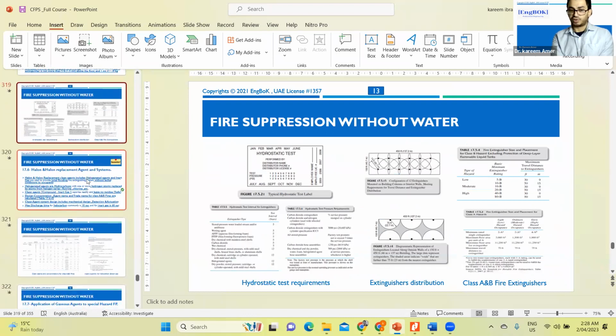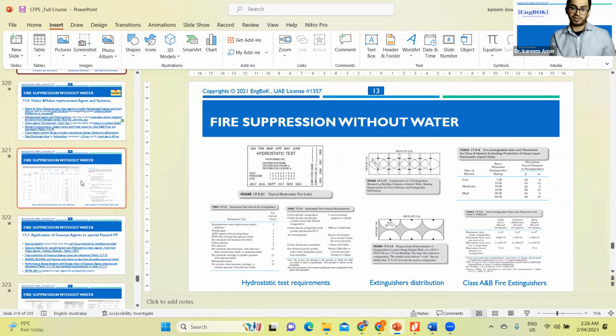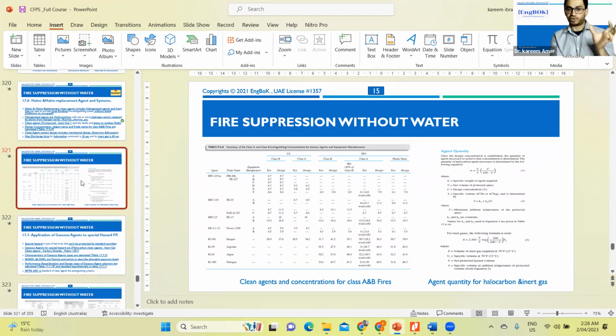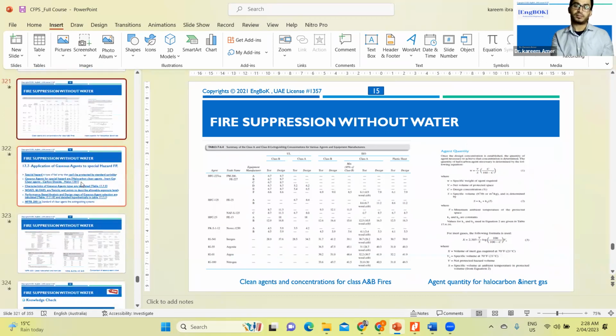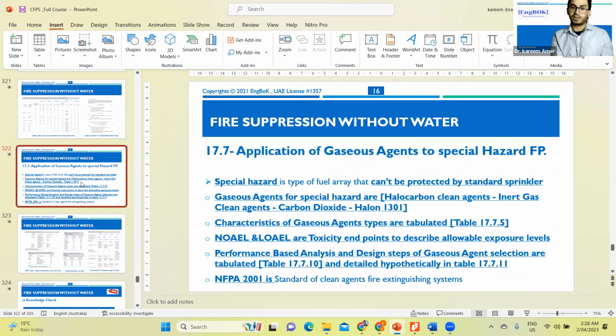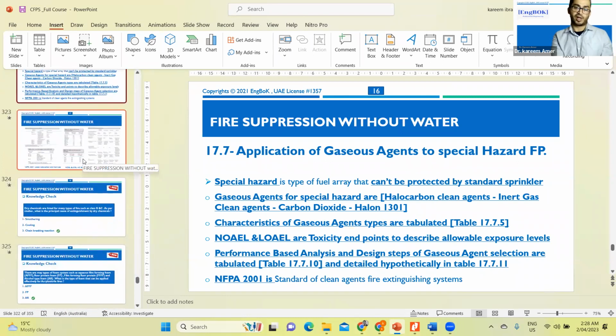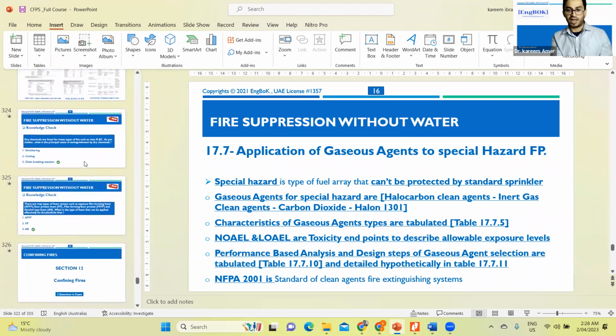Maybe fire extinguisher: you should know the classification, the use, the height of the fire extinguisher, and the weight of agent. Based on this, you could put the extinguisher in the right location, right space, and the height. Clean agent, maybe inert gas, maybe halocarbon. We have different classes of fire, A or B or C. You should understand what the lowest observed design concentration is and how to calculate the demand or the quantity, minimum quantity, or design quantity of inert gas or halocarbon agents.